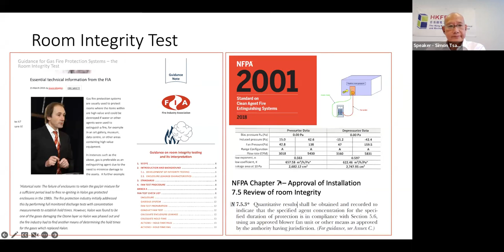The National Fire Protection Association NFPA 2001 code, Standard on Clean Agent Fire Extinguishing Systems, under Chapter 7.5, approval of the installation, on the review of room integrity, states that a quantitative result shall be obtained and recorded using an approved blower fan test or other means as approved. Guiding notes and procedures on the room integrity test are provided by the Fire Industry Association and under the NFPA code. After the integrity test or the blower fan test, a report showing the leakage area at the design pressure per manufacturer recommendations will be recorded and generated.